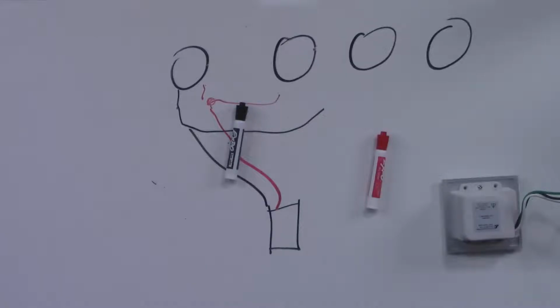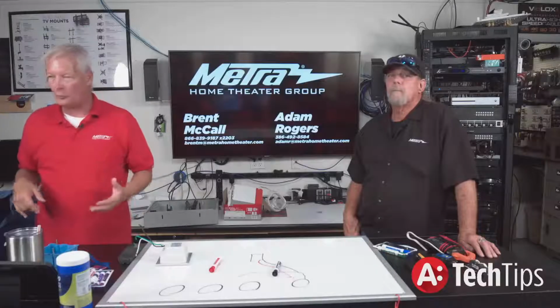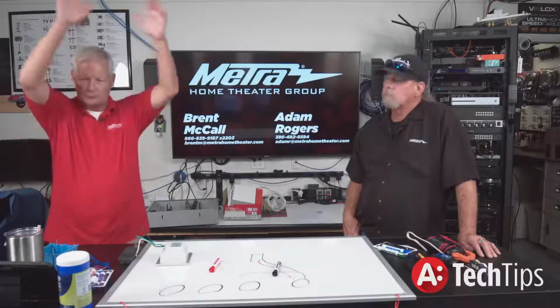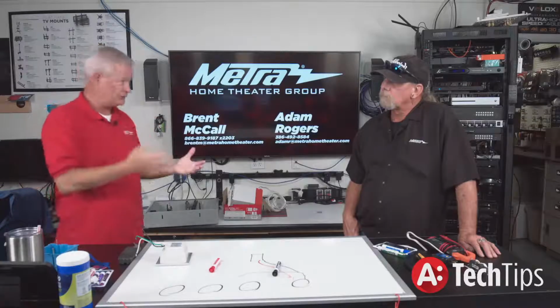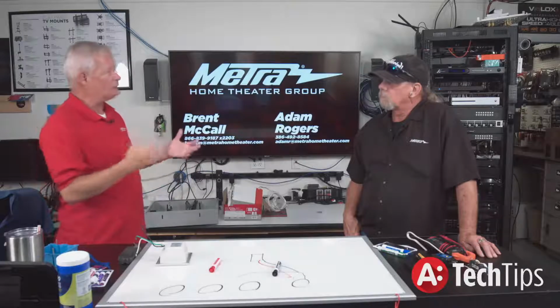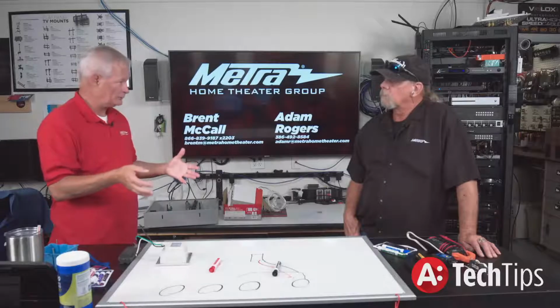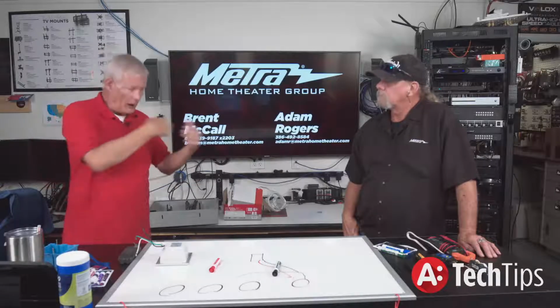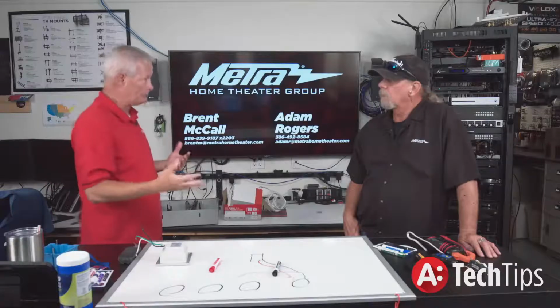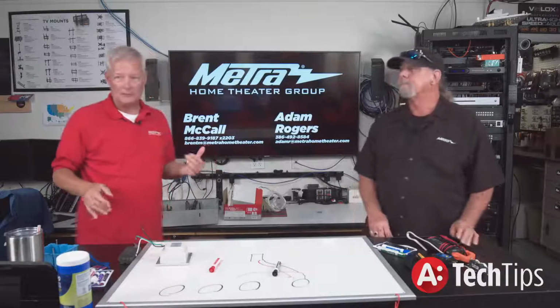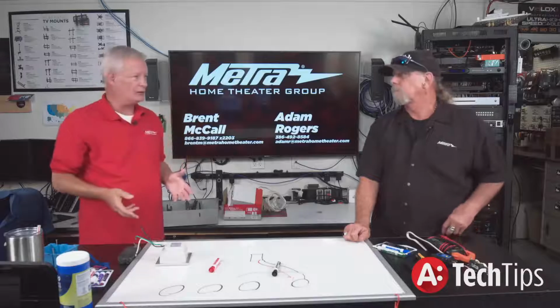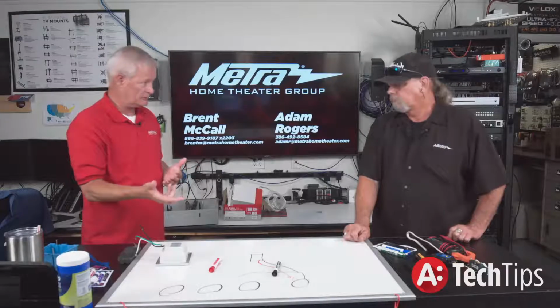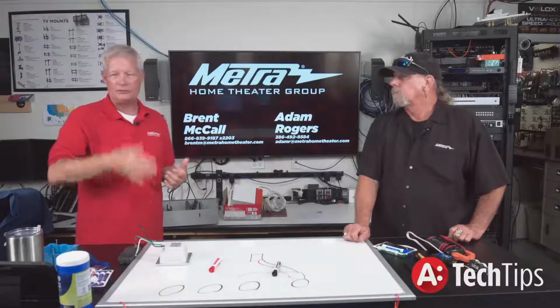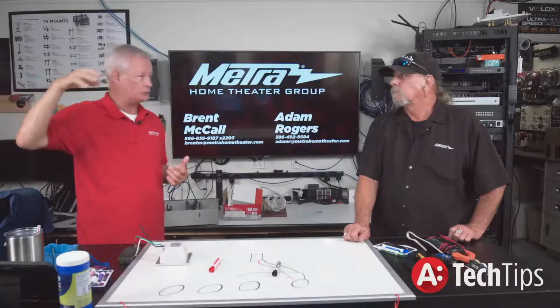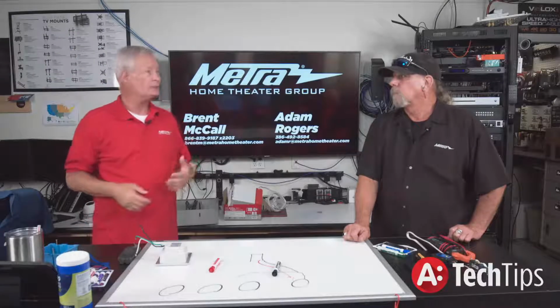Adam's question was this: in centralized lighting, whether it's Crestron, Lutron, Control4, or Vantage, you will have a centralized panel that you're bringing all the loads or devices back to. And at least on the main one, you're going to have also a controller. Now, Rob and I have always treated the controller as a separate circuit completely, because all the control running up and down inside the panels is low voltage. And we don't want to take anything, we don't want a heavy load on one of the modules, or short one of the modules, to shut down the primary master.